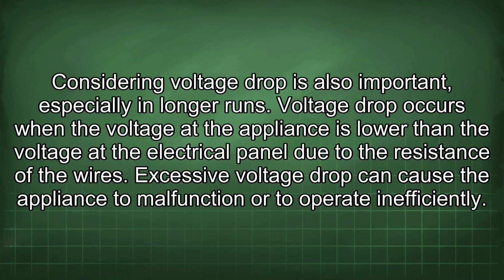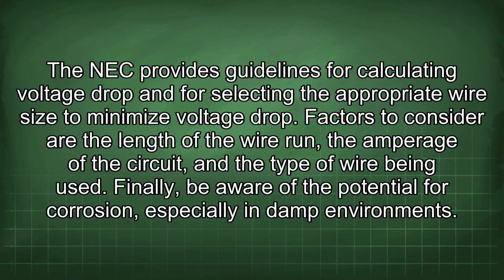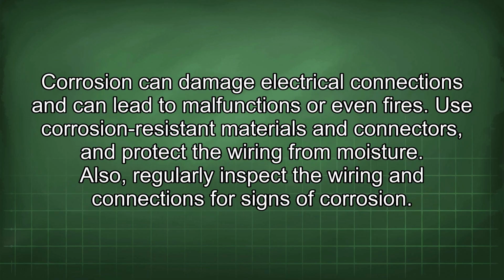Excessive voltage drop can cause the appliance to malfunction or to operate inefficiently. The NEC provides guidelines for calculating voltage drop and for selecting the appropriate wire size to minimize voltage drop. Factors to consider are the length of the wire run, the amperage of the circuit, and the type of wire being used. Finally, be aware of the potential for corrosion, especially in damp environments. Corrosion can damage electrical connections and can lead to malfunctions or even fires. Use corrosion-resistant materials and connectors, and protect the wiring from moisture. Also, regularly inspect the wiring and connections for signs of corrosion.